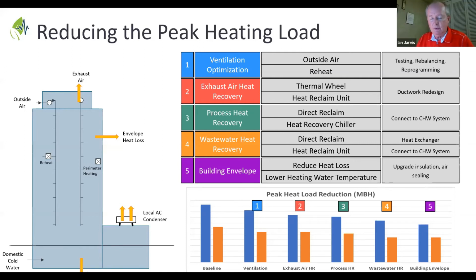Wastewater heat recovery: we've got a lot of warm and hot water leaving the building. Can we recover the heat from there? And the building envelope, and I'm hoping that Ajwad will touch on that in Nadine's conversation. Suddenly the building envelope becomes strategic, not just because it helps reduce the peak heating load and reduce the plant size, but also because it can allow lower heating water temperatures that lead to higher plant efficiencies. So in terms of plant size, optimizing that and right-sizing the plant is another element of the progression towards low carbon heating.